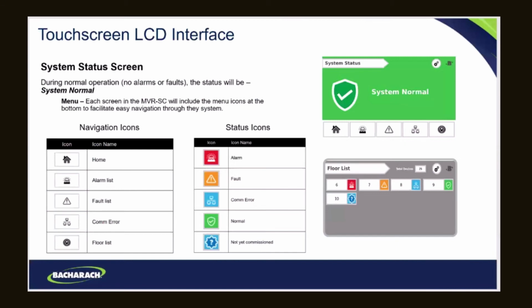Okay. So going over the touch screen interface, again, if you see this screen on your controller, everything is golden. A couple of the icons: you press on this icon, you always get back to the home screen. If there are any alarms or faults or communication errors, these icons will typically turn color, and this entire screen will move over to either the alarm screen, the fault screen, or the communication screen. This other icon here is the floor icon, and you can press it and get to your floor list, so you can look at the individual gas detectors on each one of the floors.